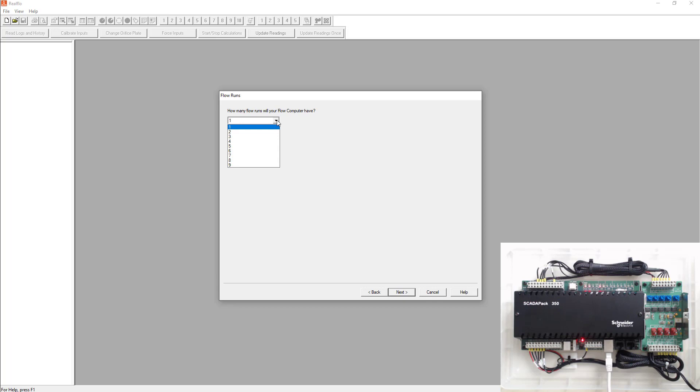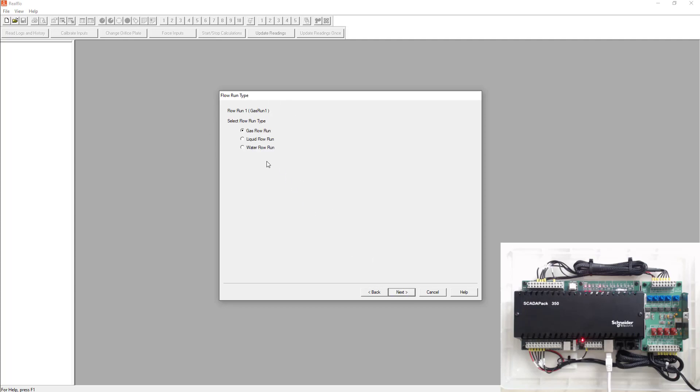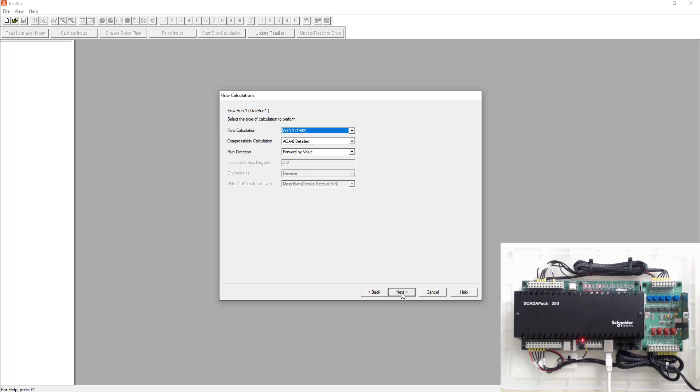Next is you're going to ask you how many flow runs you can have. You could have up to nine flow runs. You could have three gas, three liquid and three water runs in this. Initially we're just going to set up one run to start. So we're going to pick one and go next. It's going to ask you what you want to call that one run. So we'll call this gas run one. We can ask you what type of flow run it is. We're going to simulate a gas run.